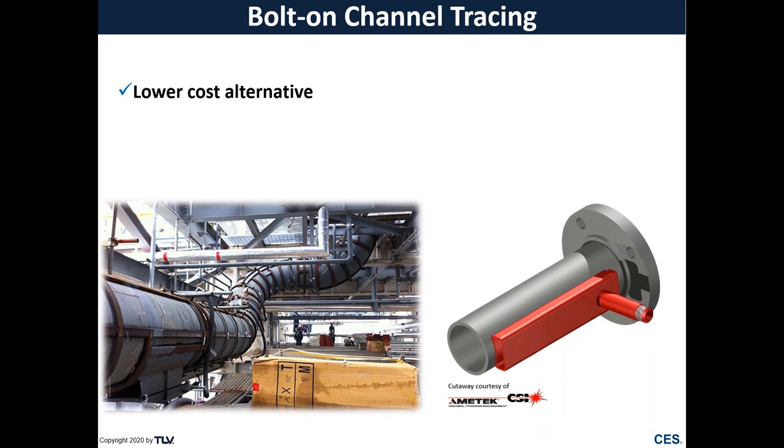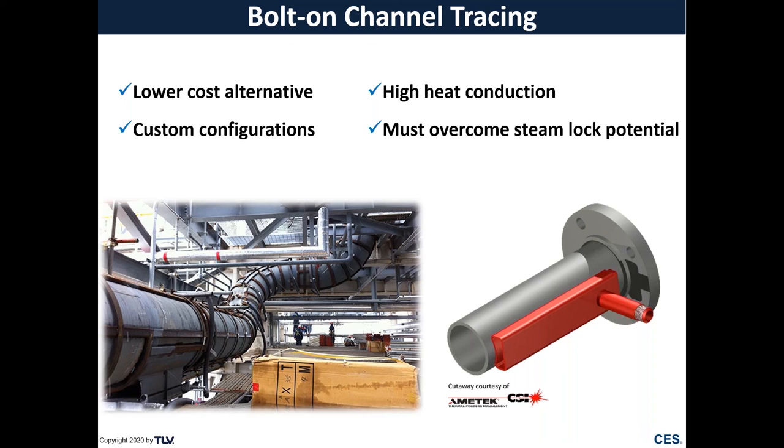This can be a much lower cost alternative as compared to jacketed piping and can be utilized in many different custom configurations, such as with piping, valving, vessels, and tanks. And when installed with proper condensate drainage that does not steam lock, bolt-on channel tracing can provide sufficiently high heat conduction.